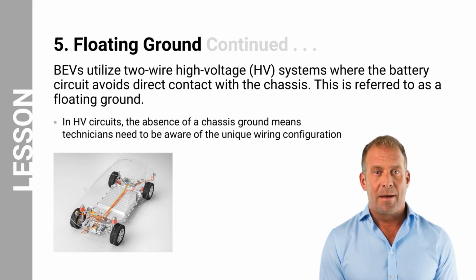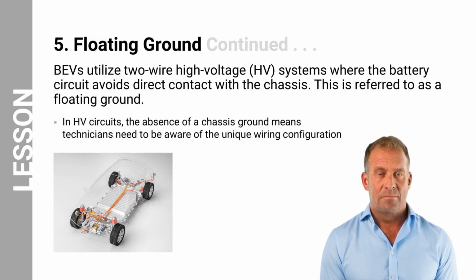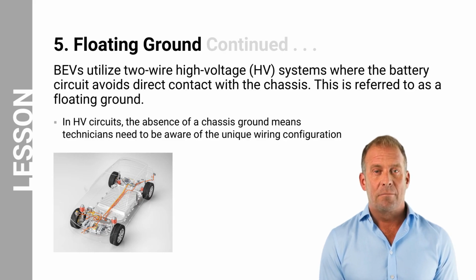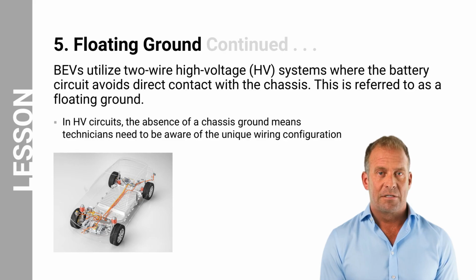High-voltage components like the battery, inverter, and motor have dedicated positive and negative high-voltage wires for power delivery and return paths. These wires are also isolated from the chassis. Technicians familiar with 12-volt systems are accustomed to identifying ground wires connected to the chassis. This grounding path allows for fault detection and protects against shocks. In high-voltage circuits, the absence of a chassis ground means technicians need to be aware of the unique wiring configuration and follow specific safety protocols. Each high-voltage component has its own designated ground wire within the isolated circuit.